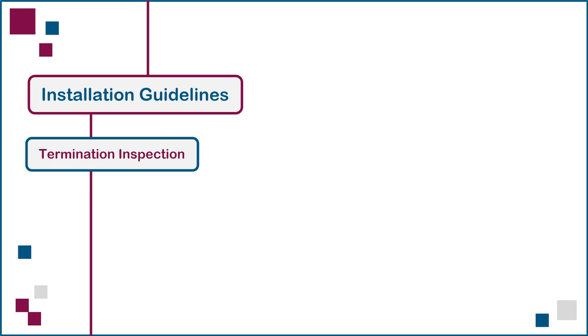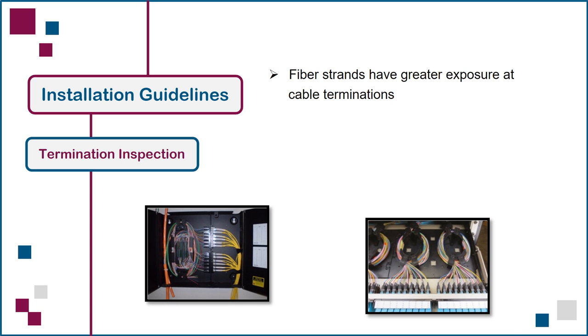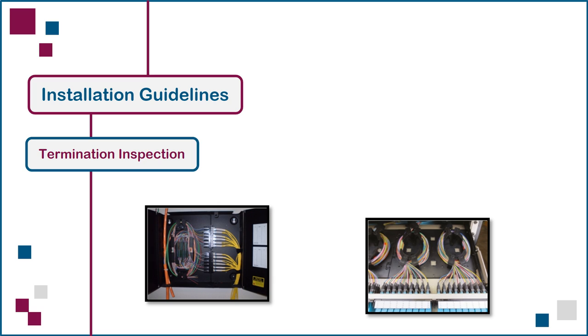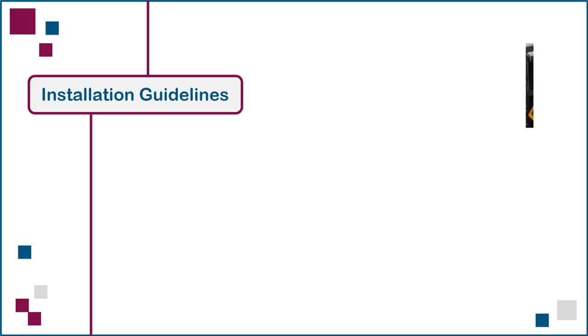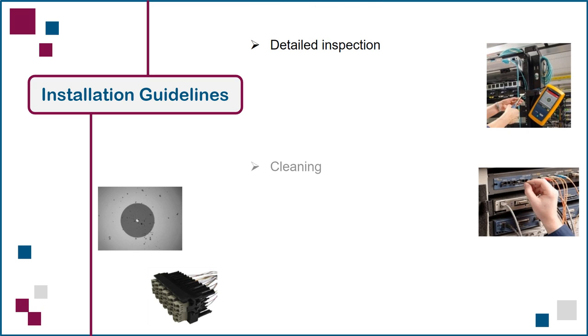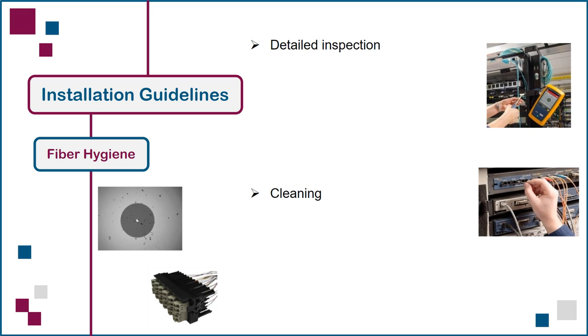When inspecting or auditing a fiber cabling installation, emphasis is usually placed on the termination of the cables at both ends due to the greater exposure of the fiber strands. Items to verify for both cables and cords include bend radius control, controlled management of excess length or slack, adequate strain relief at the connector, sufficient connector mechanical resistance to prevent easy disconnection, and labeling that clearly identifies each link. No discussion on optical fiber cabling installation can be considered complete without covering detailed inspection and cleaning, also referred to as fiber hygiene.